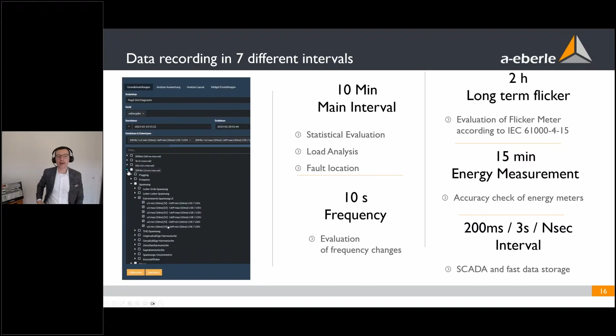We call that internally 15-minute or n-minute interval, which is time synchronized, and this is often needed for accurate check of energy meters, for active energy control systems, and so on, as well as for SCADA and fast applications. The device has 200 milliseconds, 3 seconds, and a free interval, which we call n seconds. So you can decide between 1 second and 60 seconds with all these parameters. And here on the left-hand side, you can see some parameters which can be recorded.